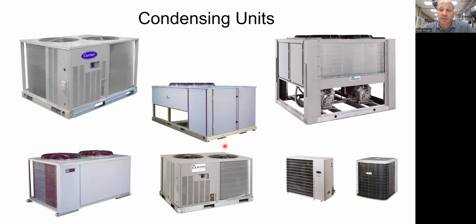Another one would be, not always, but sometimes, computer room units. So you've got an old computer room in a building where they have that raised floor and they pressurize the floor with air. And then there's a Liebert unit in there. That Liebert unit might have a compressor in it. And then there's a condenser outside. That's a fan and a coil only and no compressor outside.